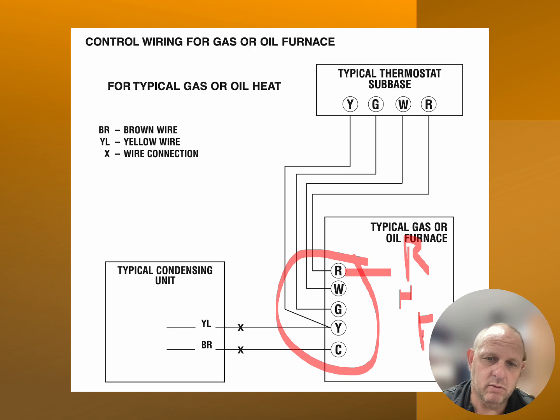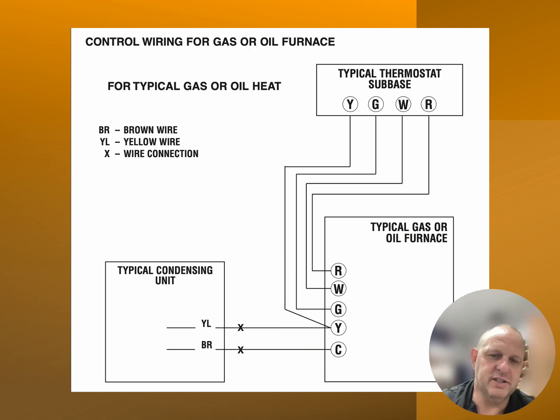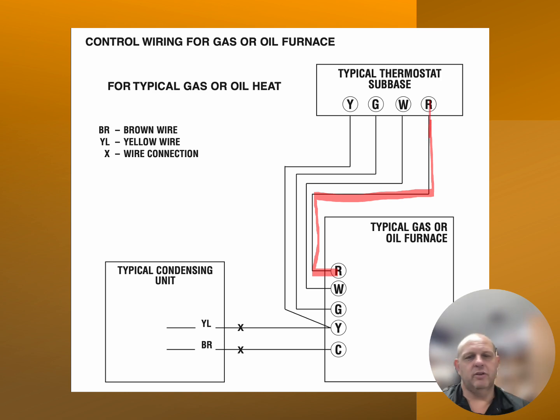Now we'll try our best to write fan out. Okay, Y is the cooling. Okay, so what happens here is power comes up from the indoor unit into the thermostat. The thermostat's going to receive that 24 volt power in there. What is a thermostat? A thermostat is a switching device, and that's all it is. After the thermostat says, hey, our building's getting too hot, it's going to send out power. And this is sequence of operation. It's going to send out power through the G terminal. It's going to send out power through the Y terminal.